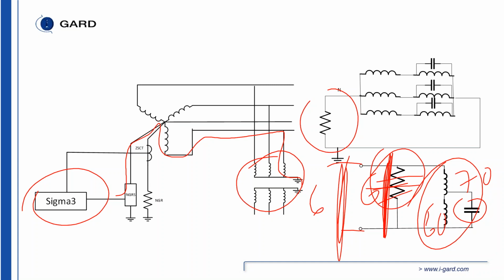When we get into a value that's smaller than 6 ohms, we utilize a second frequency to determine what that resistance is going to be or should be. Okay. So don't think of a potential pressed upon this. We have a frequency that's put on this, and we're measuring that impedance.